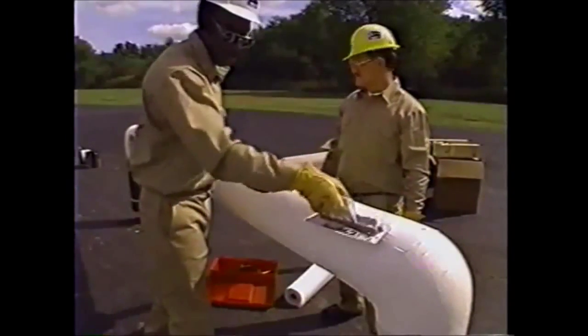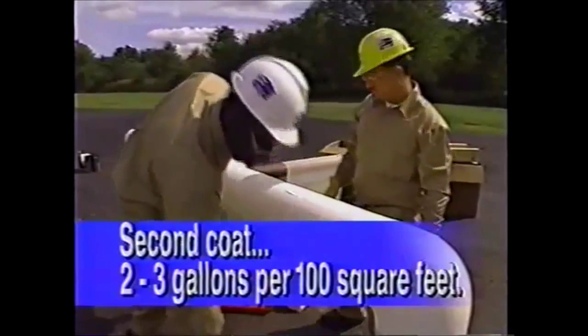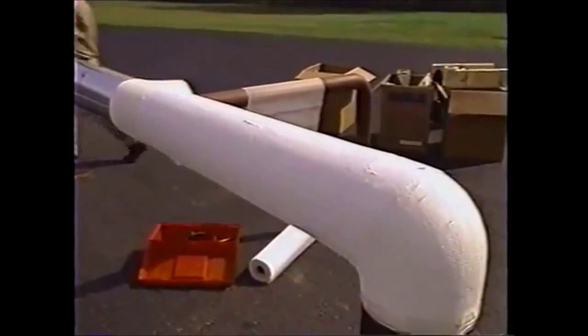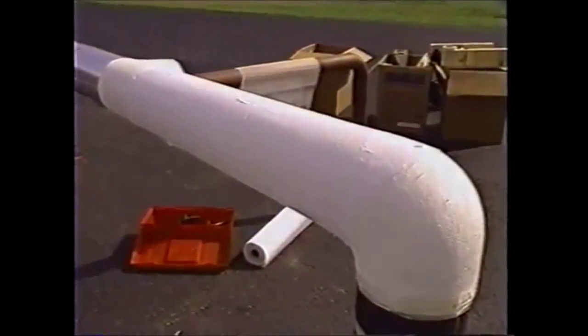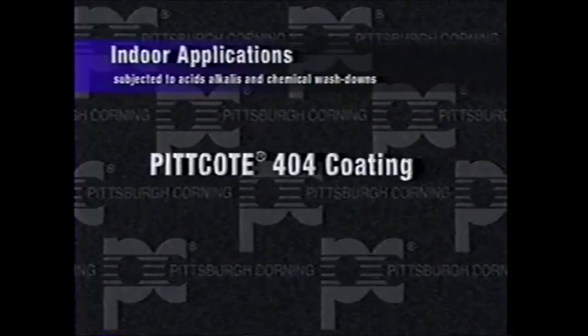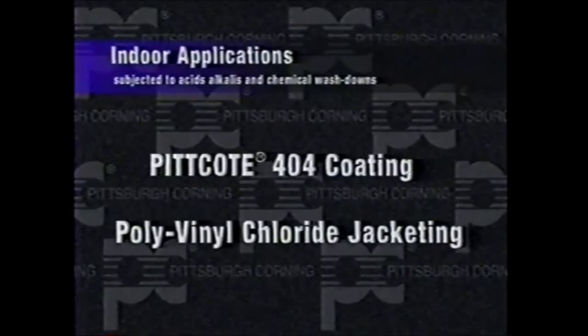When the first coat dries, trowel a second coating of Pittcote 404 at a rate of two to three gallons per 100 square feet. Continue this application until the entire pipe is coated. For indoor applications subjected to various concentrations of acids, alkalis, and chemical washdowns such as pipes in the food processing industry, use Pittcote 404 coating or polyvinyl chloride jacketing over the insulation.